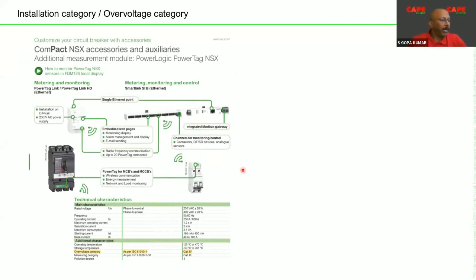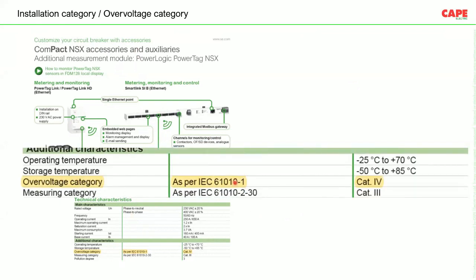Now, for transient over voltage protection or surge protection, I will switch off my video for a short time. The first parameter which we are supposed to identify or mention is the voltage impulse withstanding capacity. So here, for example, I am showing a catalog from Schneider. You can see here the over voltage category as per IEC 61010. This is category 4. That means this device can be used at the mains incoming panel.